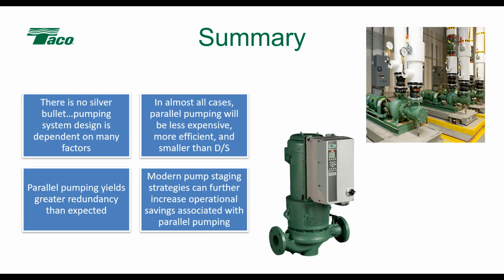Nice, nice. And then it's a statement from Bill, and I'm sure you'll expound on it. We always make the pump non-overloading in VFD with enough capacity to match motor horsepower. We have run both fans and pumps over 60 hertz if needed. Had no problems. Lucky you, Bill. We still cringe whenever it happens.